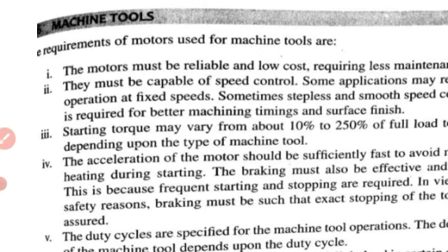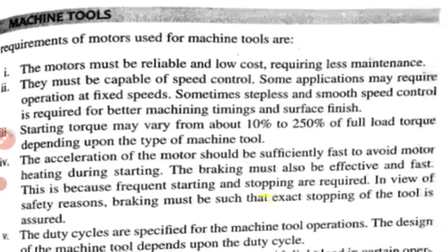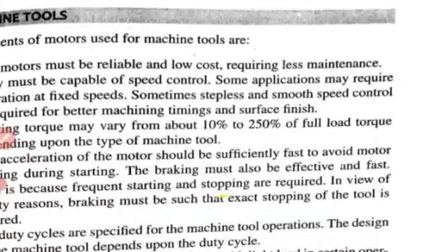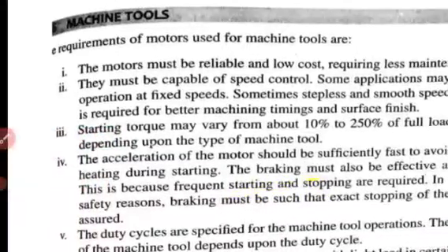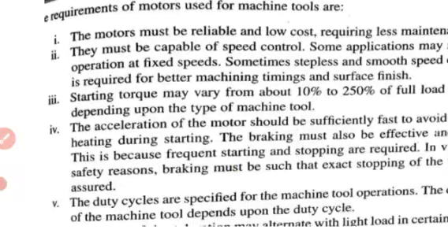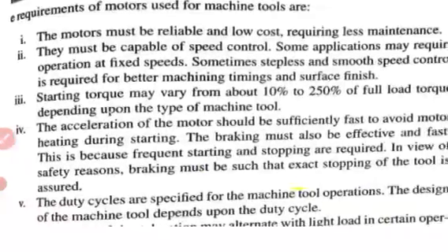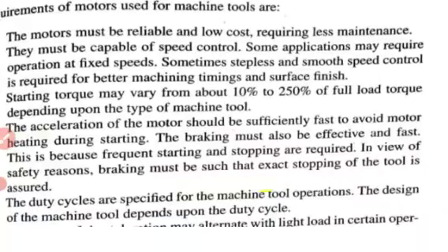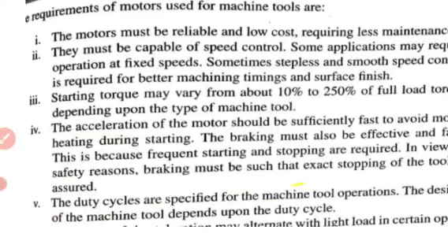Starting torque may vary from about 10 percent to 250 percent of full load torque, depending upon the type of machine tool. The acceleration of the motor should be sufficiently fast to avoid motor heating during starting.